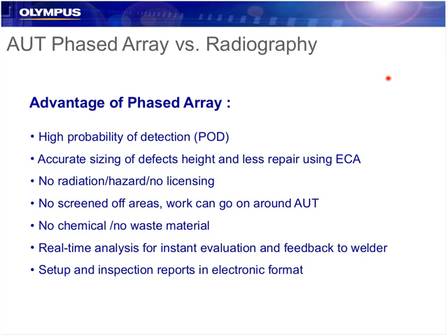So obviously ultrasound is a safe alternative, and it's really good for other processes to go on at the same time. Typically no chemical, no waste material. Our coupling is just water, or if it's a very cold condition, we might use a methanol mix, but that can usually be captured. We don't really have any waste material from producing film, this kind of thing. And one of the huge benefits is real-time analysis.